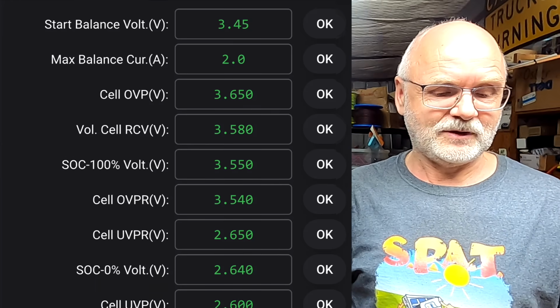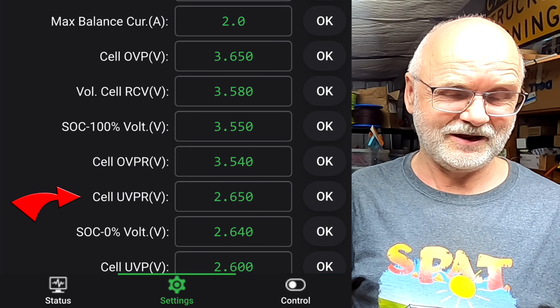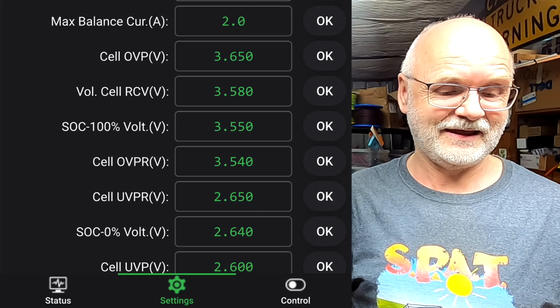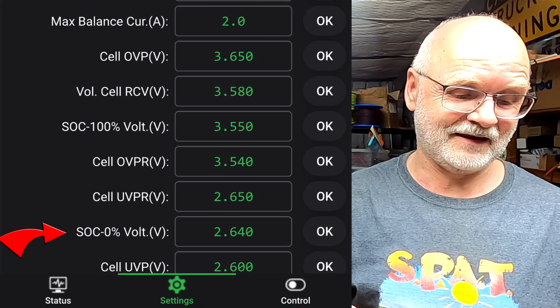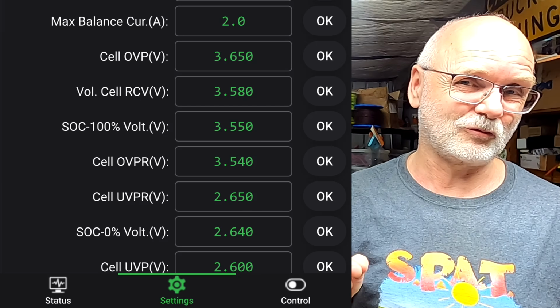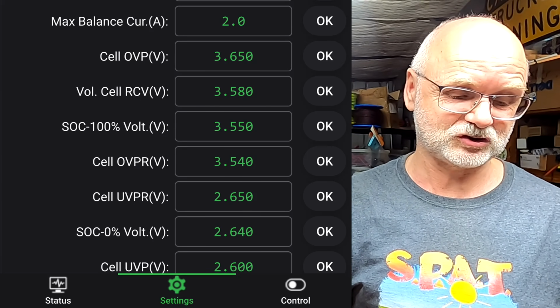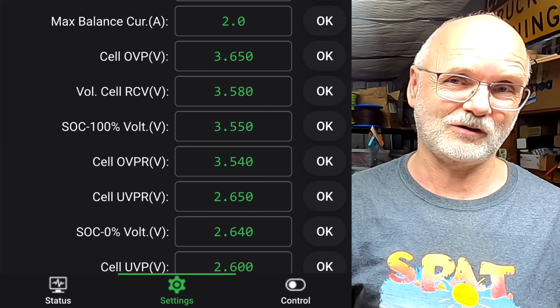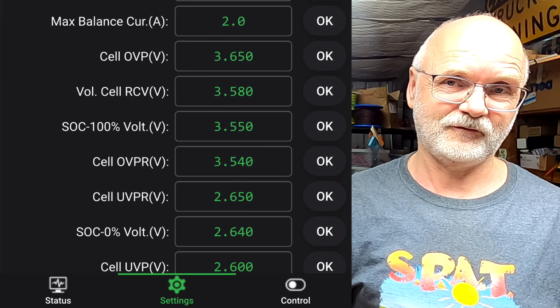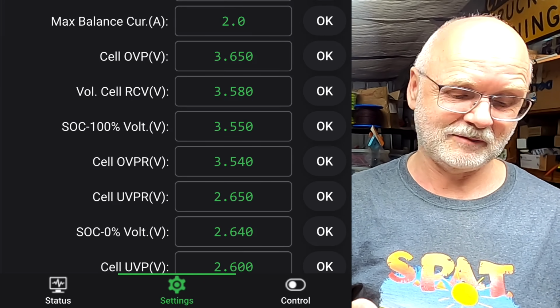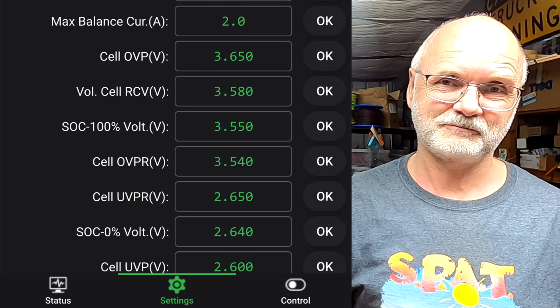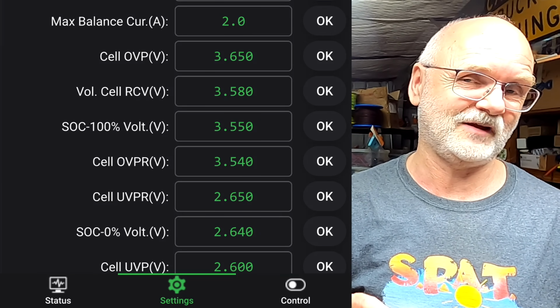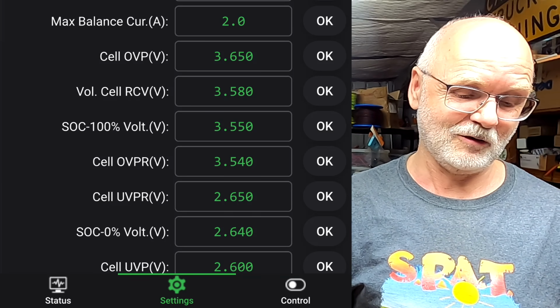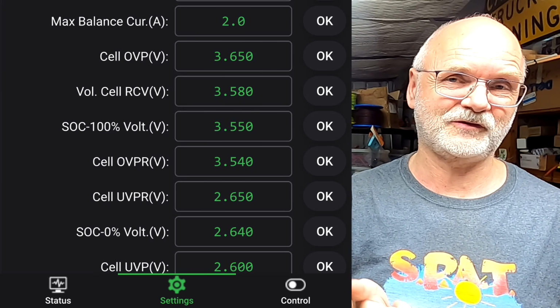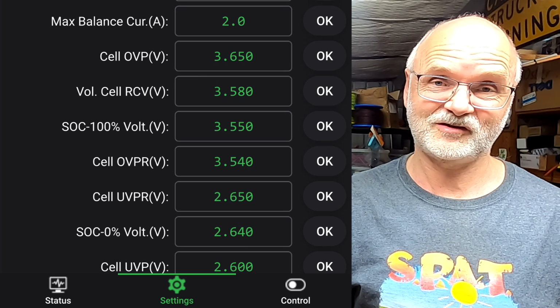Then we have the cell under voltage protection recovery, and we also have a state of charge 0% voltage. So you not only can reset the BMS to 100% state of charge, you can also set it to 0% at a certain voltage. So if you, for example, stop discharging at 2.64 volts, it will then show 0% state of charge. You can use this to have very defined points, 0% and 100%. That is brilliant - no other BMS has got this function.